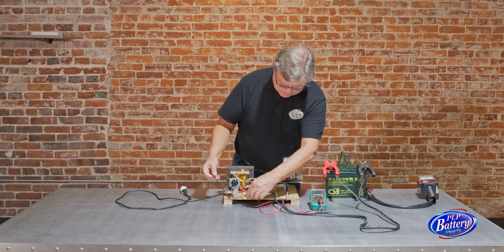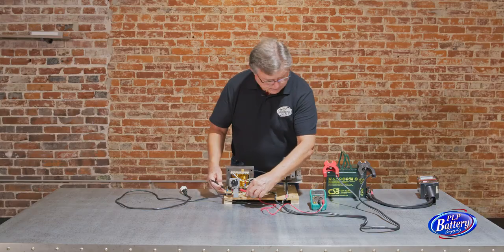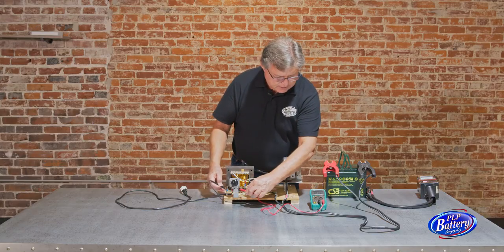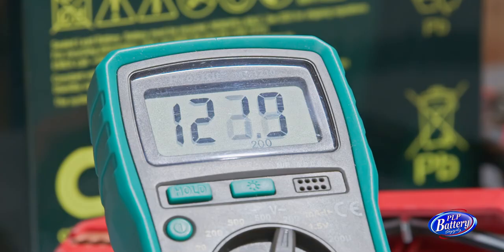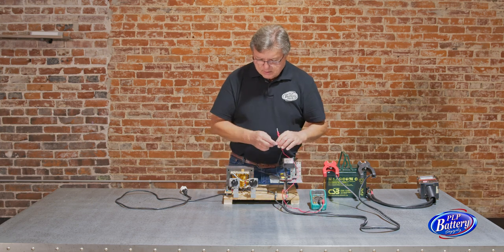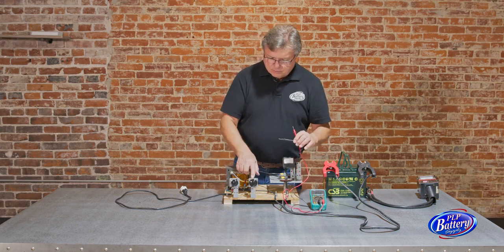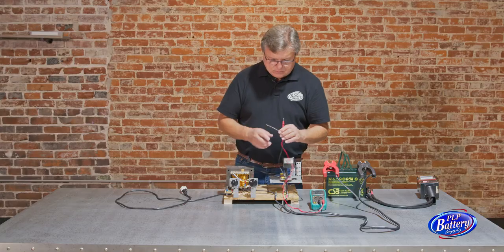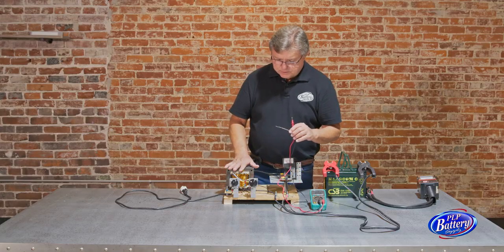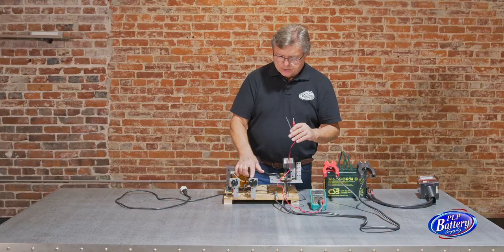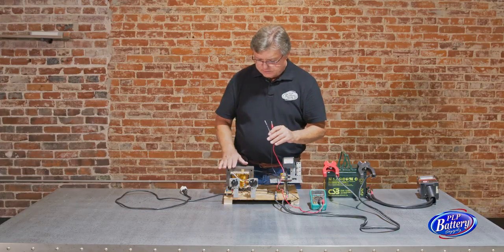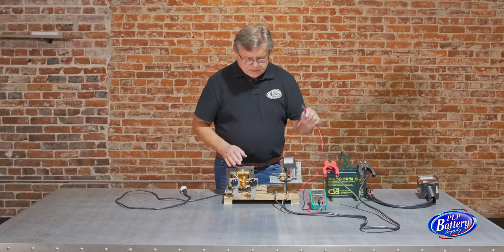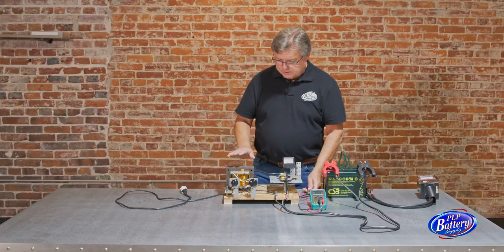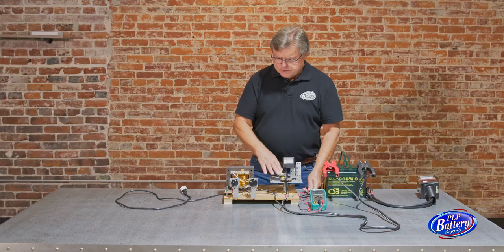So if I test right here, and then just come over here to ground, that's showing me that our AC input into this charger is 121 volts. That's pretty typical for line voltage. All of these are going to remain the same voltage as they come into the transformer. So it's just diverting from one to the next, to the next, to the next circuit in the transformer. The next voltage that we're going to see any change in is this secondary AC voltage as it goes into the rectifier.